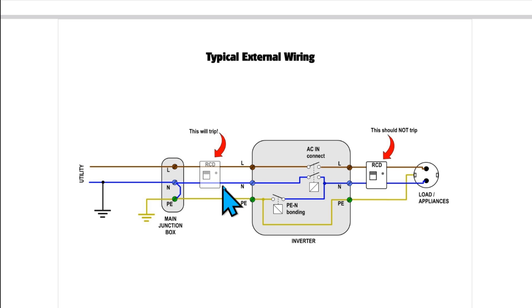And when this opens we need to recreate this bonding through this contact. However it is important to consider that if we have an RCD which is typical, this would trip because it is important not to make this floating, never floating. So there is a brief moment in which both contacts are closed, so here will flow a current through the neutral.